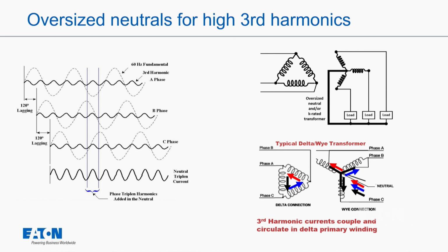So if you have VFDs, for example, I'm not going to oversize my neutral on my system unless I have those VFDs connected line to neutral. If I have a bunch of computers or LED lights or any other loads that produce a lot of third harmonics, then I need to consider whether or not I need to double the size of the neutral. And that goes all the way back to the transformer as well. So don't forget, just because you're oversizing the neutral here, you also have to oversize the connections all the way back to that neutral point on your transformer, which means the tabs directly inside the transformer as well.